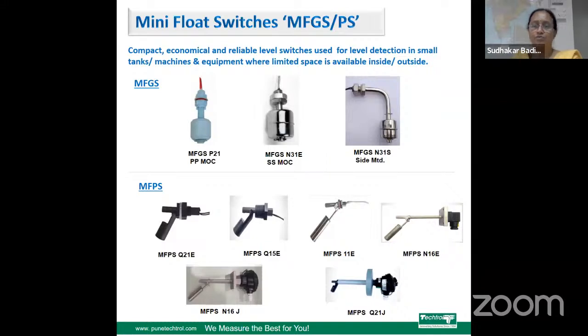This one is a miniature type float switch. These are top mounted switches or side mounted switches. They are economical, compact and reliable switches for level detection in small tanks or equipment having limited space. So here you can see various types of switches in different material in PP and SS MOC with different process connections like 1/8 inch NPT, half-inch BSP, then MFPS. Here also you will have it in the PP and SS MOC. Some of them are provided with the flange connection and enclosure also, and some of them are with potted cable connection.